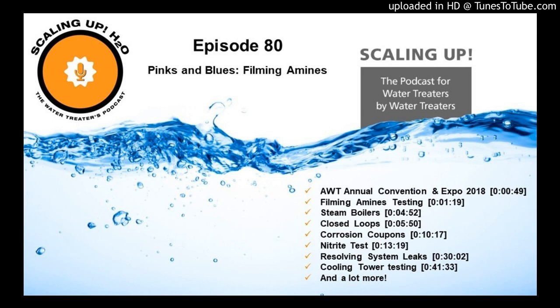And you will also notice that the nice black surface on the lid of the filter feeder, of course, that was the magnetite, you can see that that is getting stripped off. So exactly what we thought was going to happen, that anything that was on a metal surface, anything between that metal surface and the Filming Amine, that Filming Amine is going to clean that off, including our previous corrosion protection. So you can see that very thing happening as you see my presentation on my show notes page. And I went ahead and ran some through syringe filters, and you can see when we filtered out the water that had a black tinge to it, it looked exactly like the filters when we originally took those out. So I am surmising that that is the magnetite getting cleaned off of the surfaces.